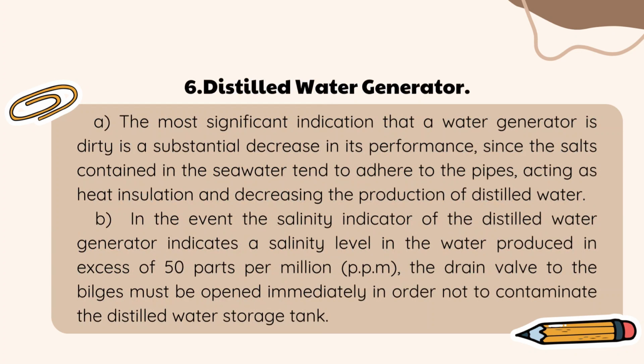6. Distilled water generator. A. The most significant indication that a water generator is dirty is a substantial decrease in its performance, since the salts contained in the seawater tend to adhere to the pipes, acting as heat insulation and decreasing the production of distilled water. B. In the event the salinity indicator of the distilled water generator indicates a salinity level in the water produced in excess of 50 parts per million, p.p.m., the drain valve to the bilges must be opened immediately in order not to contaminate the distilled water storage tank.